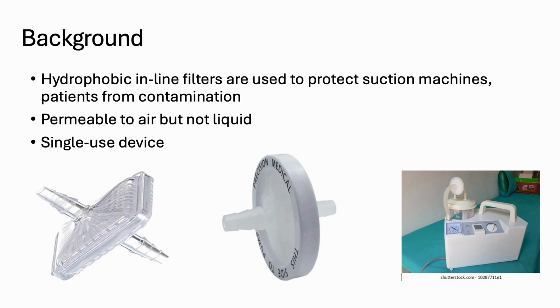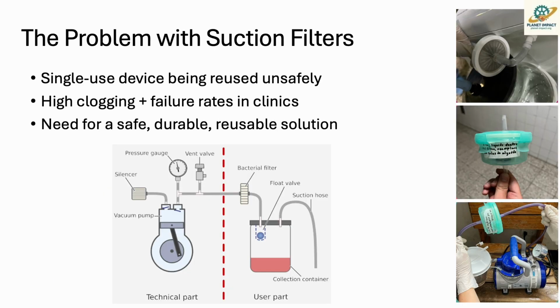This is the industry standard filter used in the clinics we visited. It's made for single use. The mesh clogs quickly, the housing can't be opened or cleaned, and after repeated cycles, the seal becomes unreliable. So when it gets reused over and over, it becomes a risk: clogged flow, leaks, contamination, and damage to the vacuum pump.